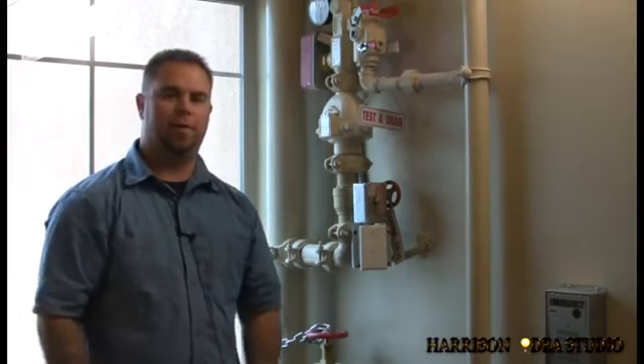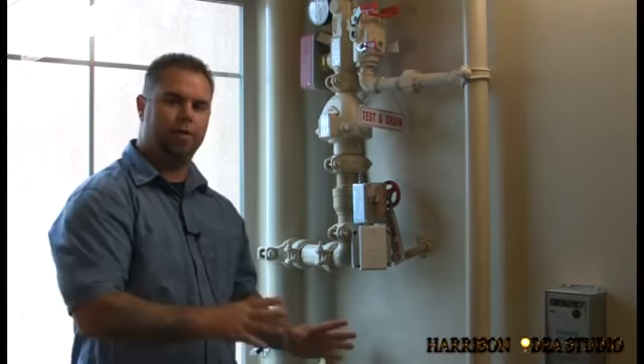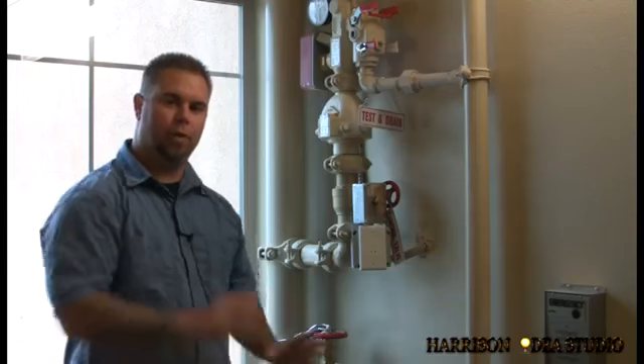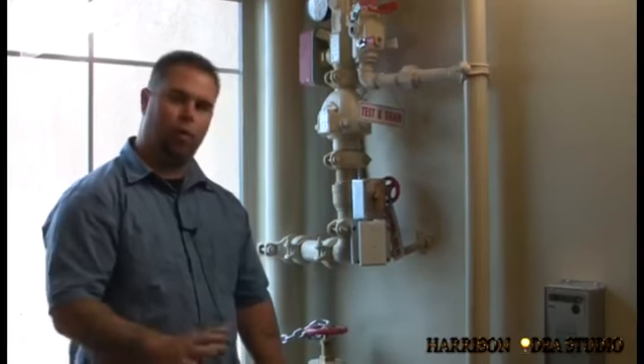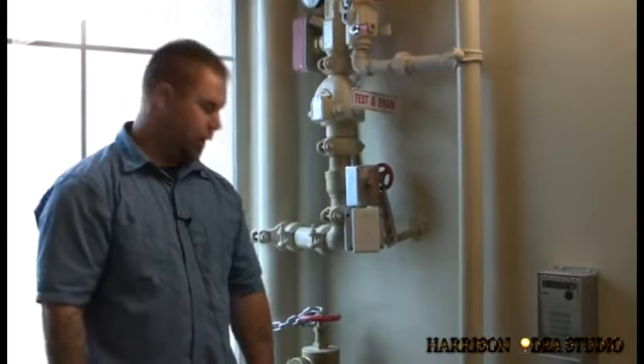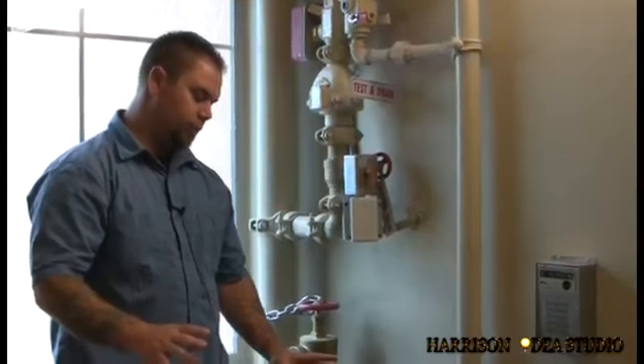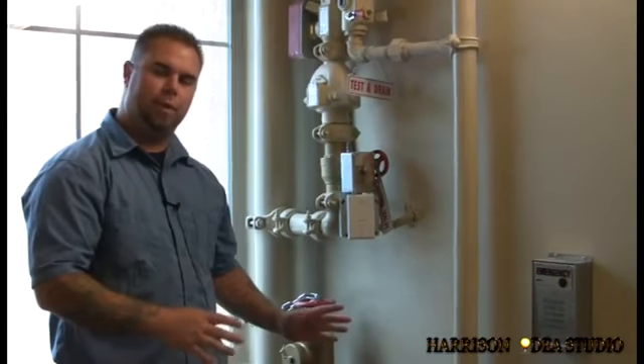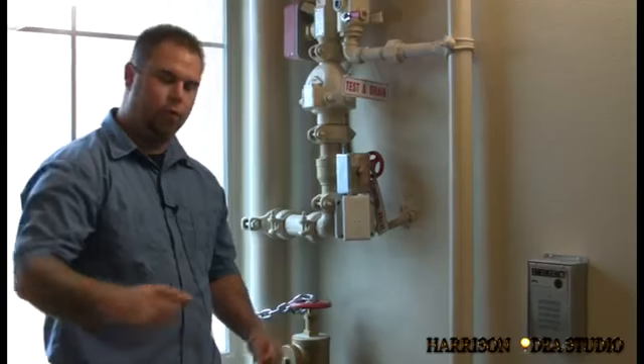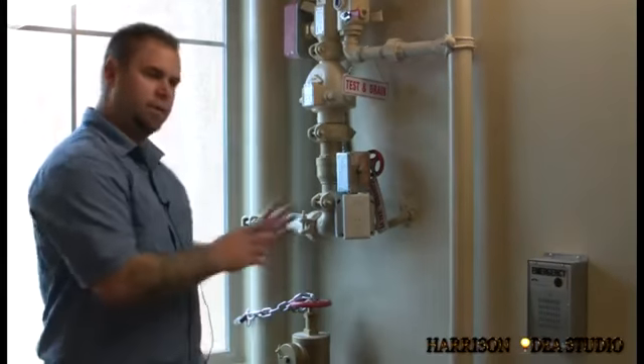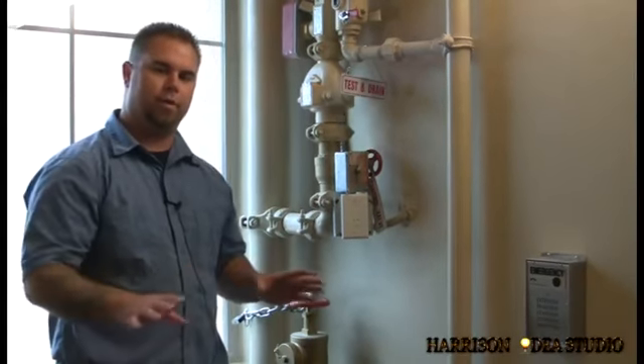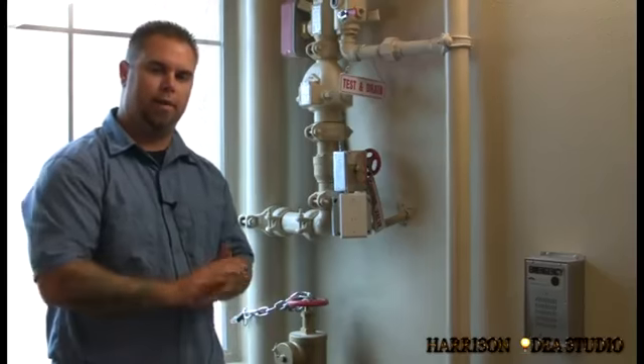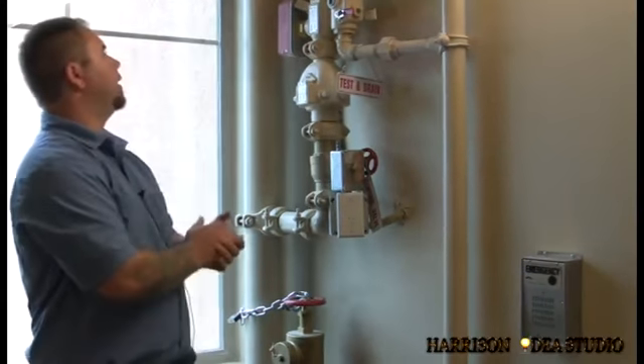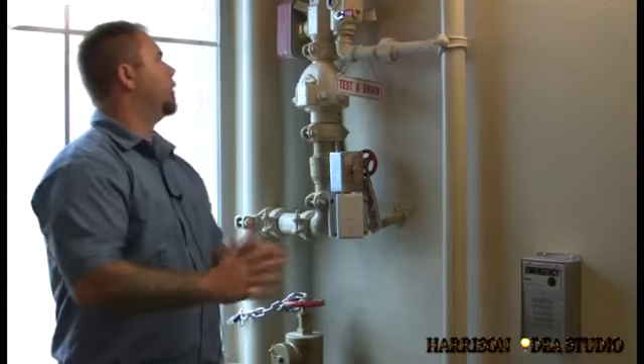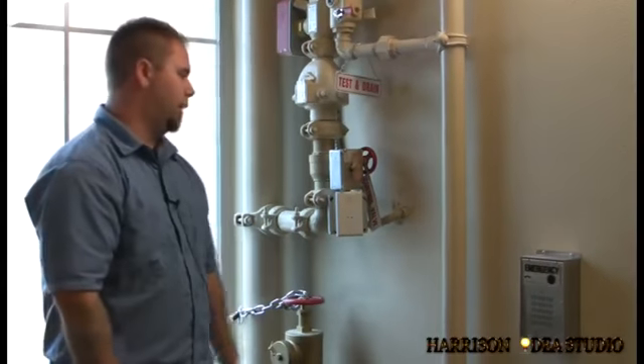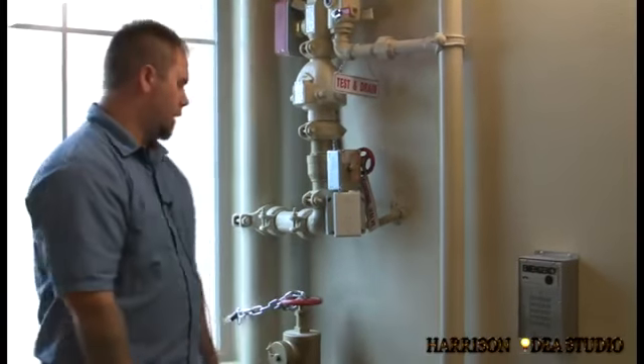This is your typical fire sprinkler riser floor assembly. Every floor is pretty typical. The supply is fed from the city water main, runs up to the building, and the system is pressurized at all times at city pressure. Pressure out here is approximately 90 psi, and that will be on the system all the time.